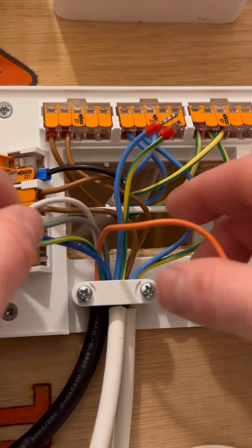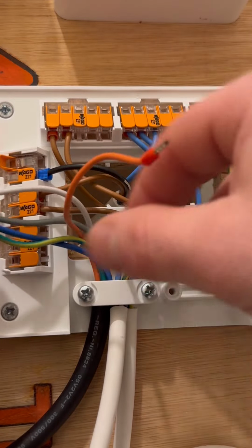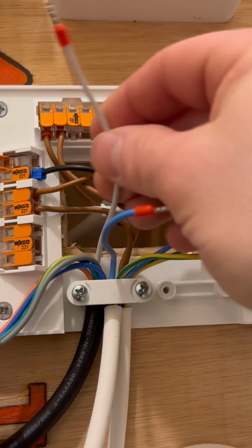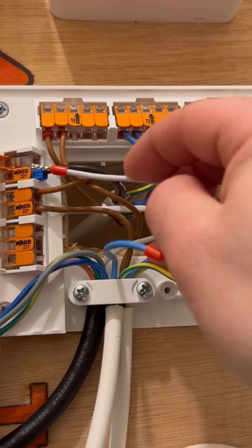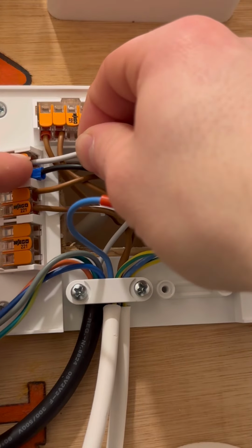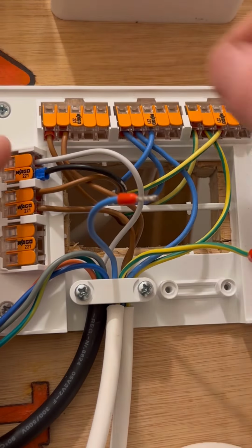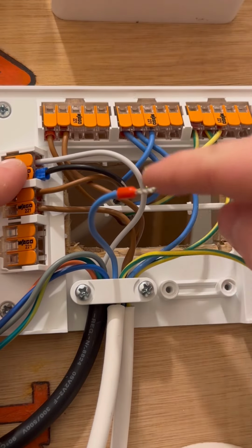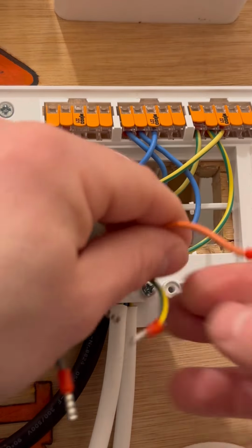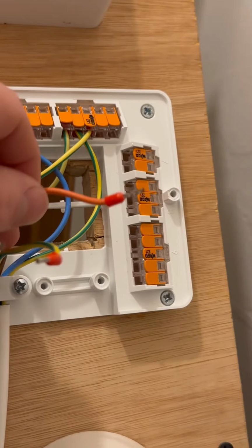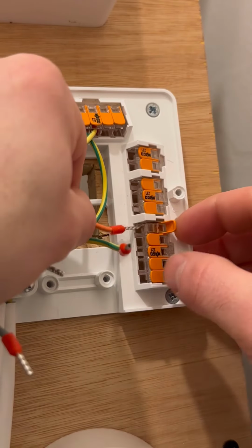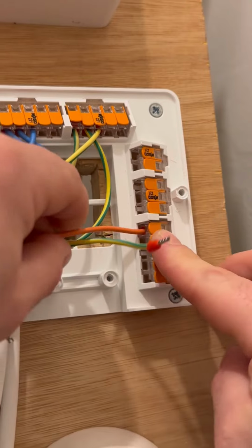Right, looks like loads of cables, but it's not that bad. So after the room stat, the call in comes to white. So we've got our heating down this side, and I'll do hot water down the other side. Once it goes through the 3-port valve, it fires the boiler on orange. So we're going to put our orange over here. Put that into there, like that.